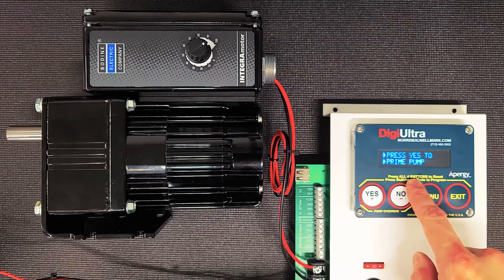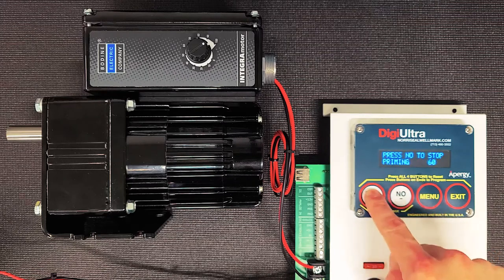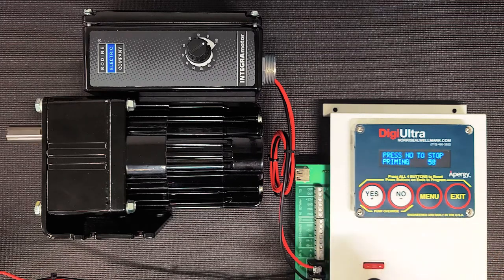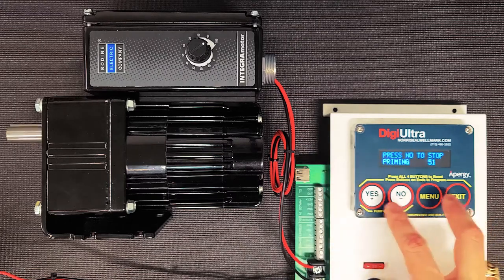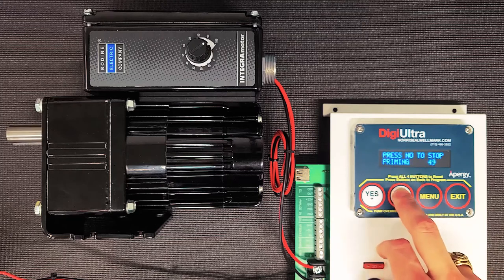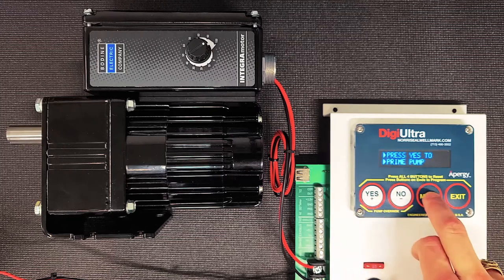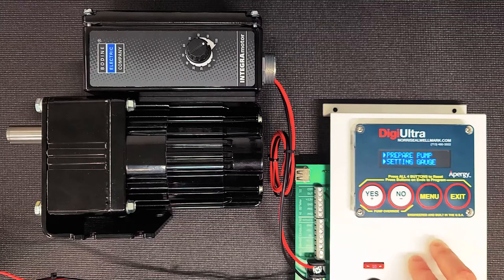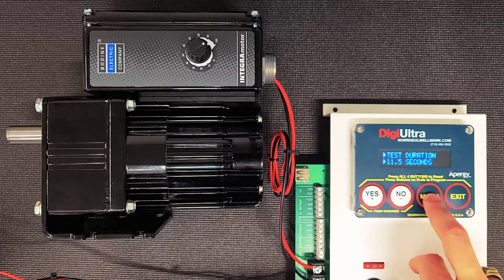The first screen is going to allow you to press yes to prime the pump, and what this is going to do is let you basically bleed down the rate gauge or prime the pump, whatever you need to do to get ready for actually testing the pump itself. You can press no at any time to stop the priming, and that'll shut the motor off. The next screen is going to tell you to prepare the pump setting gauge, and this screen just acts as a buffer, so that it gives you some time to go over to the pump setting gauge, isolate it, and mark what the current level of chemical is in the pump setting gauge. From here, press menu to scroll to the next screen.